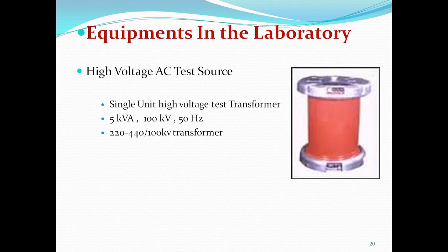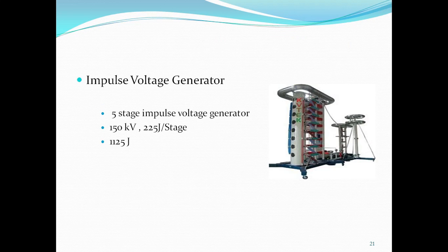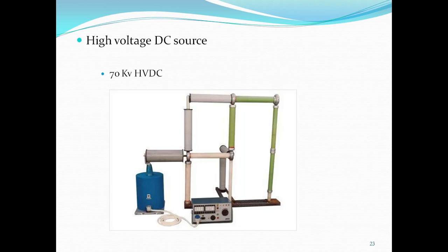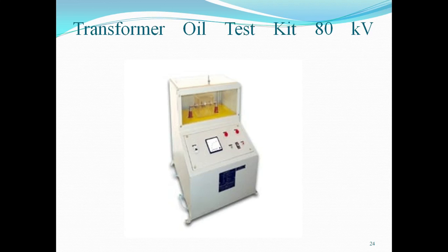Number one is the high voltage AC test source, a single unit high voltage test transformer, rated for 5 kVA, 100 kilovolt, 50 hertz, primary side 220 to 440 volt, and secondary side 100 kV. We also have an impulse voltage generator, a multi-stage impulse voltage generator, 150 kV, 225 joule per stage. The overall energy rating is 1125 joule. We also have a high voltage DC source rated for 70 kV DC, and a transformer oil test kit rated for 80 kV. So we can test transformer oil with the help of this oil test kit.